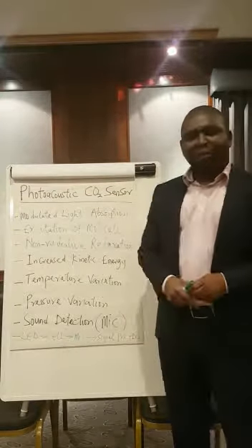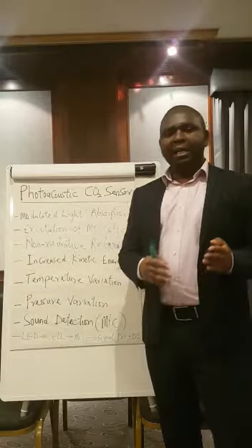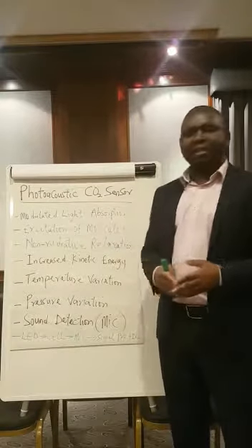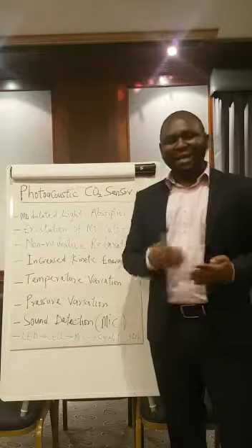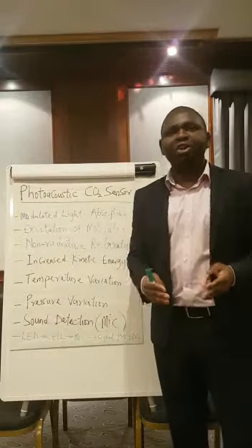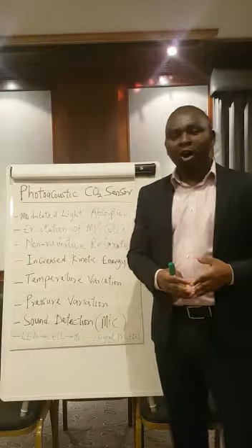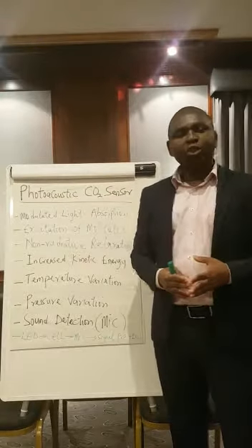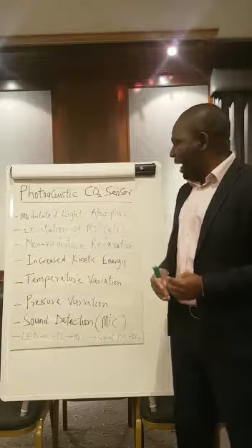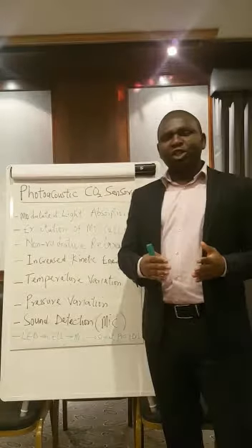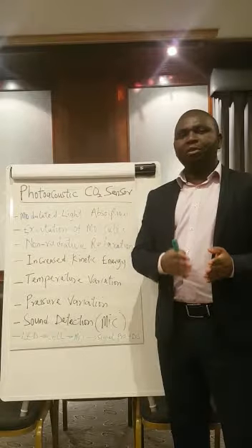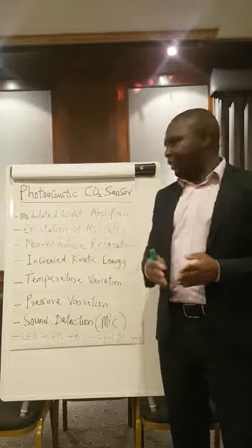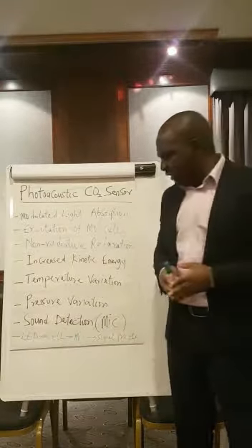Now, in my particular application, the light source is a mid-infrared LED because CO2 has a characteristic absorption signature in the mid-infrared of about 4.26 microns. And there is an electronics that I designed that leads to the modulation of that radiation at the frequency of interest based on the cell design.